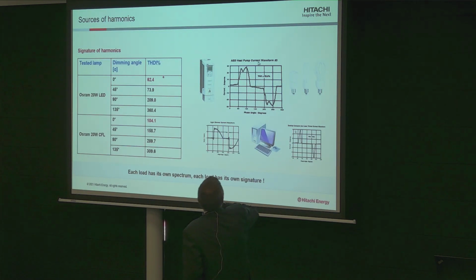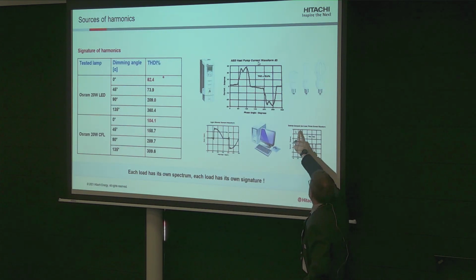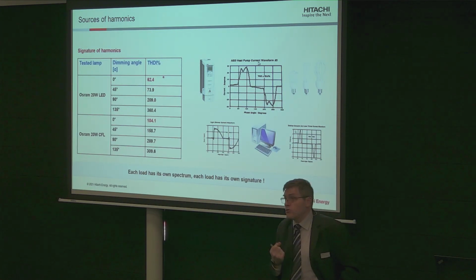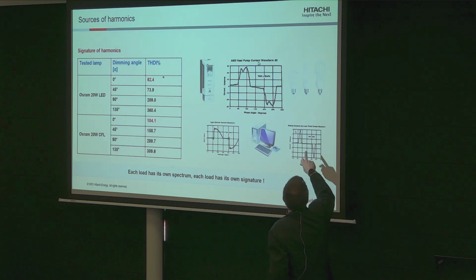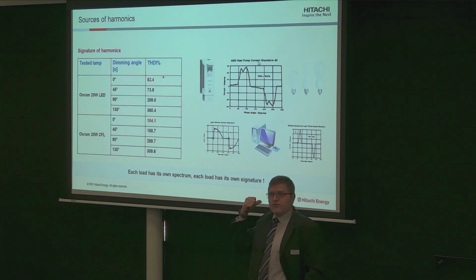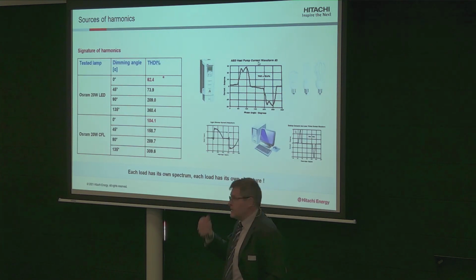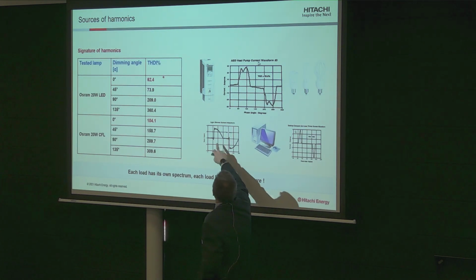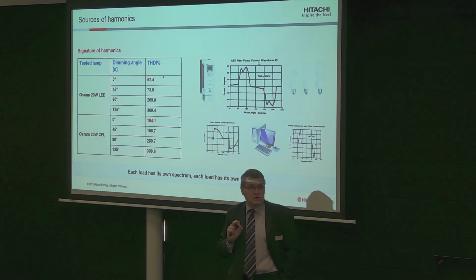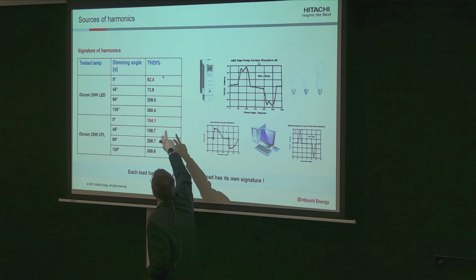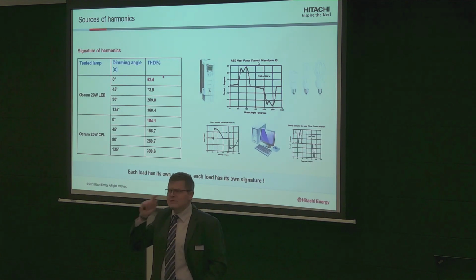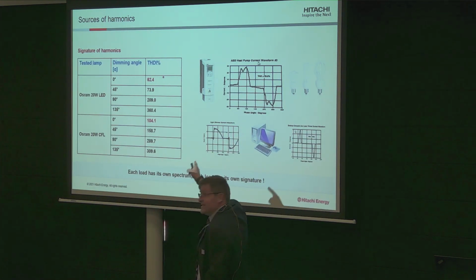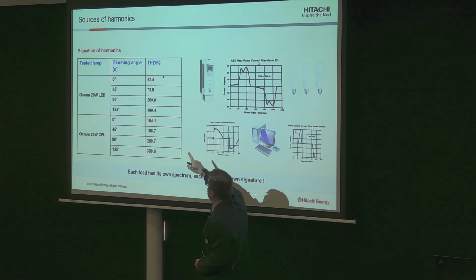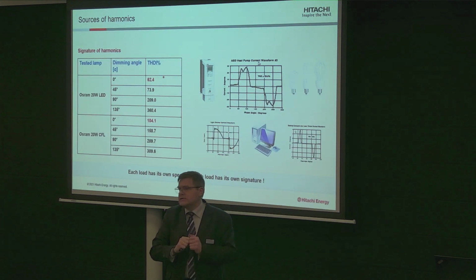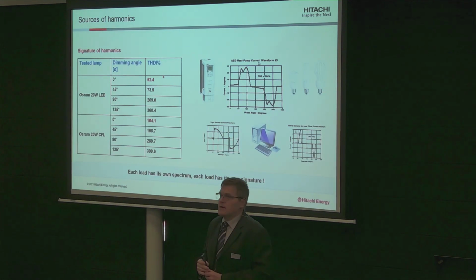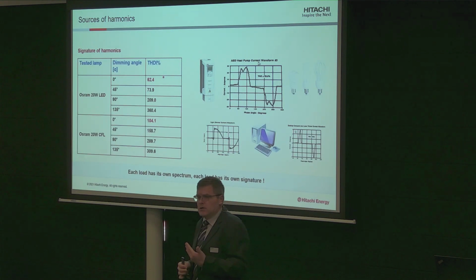Here it's just to show you, for example, your computer. This is the current that your computer draws from the network. And here we have a THDI of 140%. Alors, this is not coming from Hitachi, this is coming from a public lecture. You can find it on the internet. Here, this is a light dimmer lamp. You see how distorted the current is. And for LEDs, the dimmer, very good. You change the dimmer, but sometimes you hear some sound. This is very likely coming from the harmonic content, and then I make the parallel with the emission and EMC regulation. So the higher the harmonic pollution.